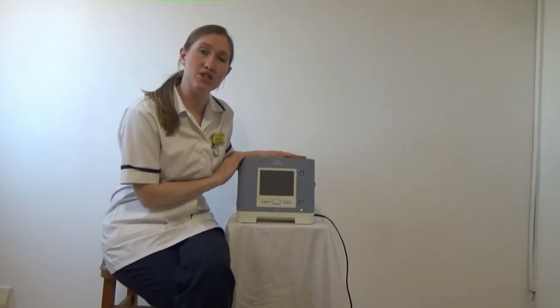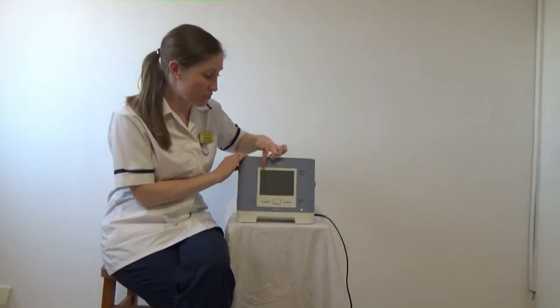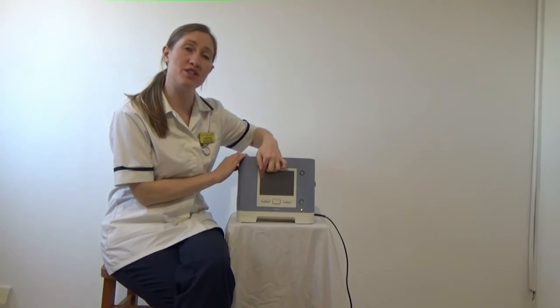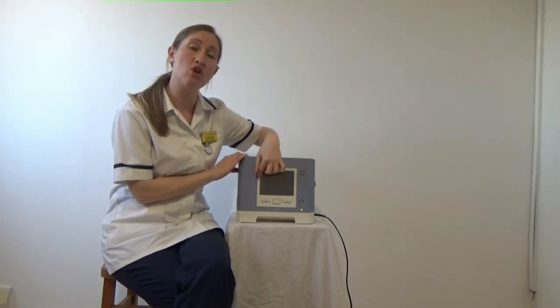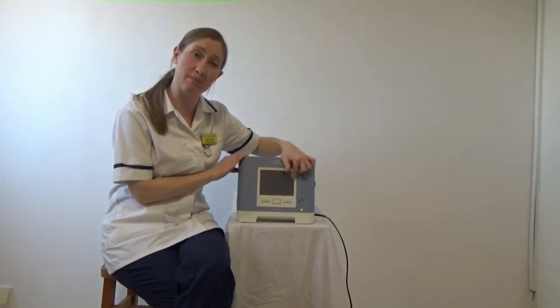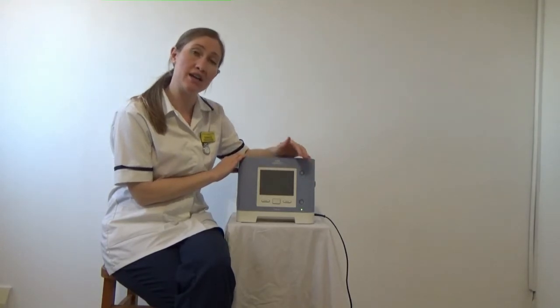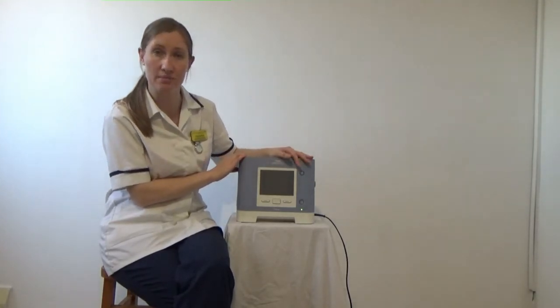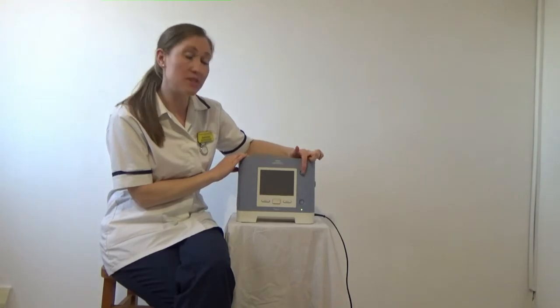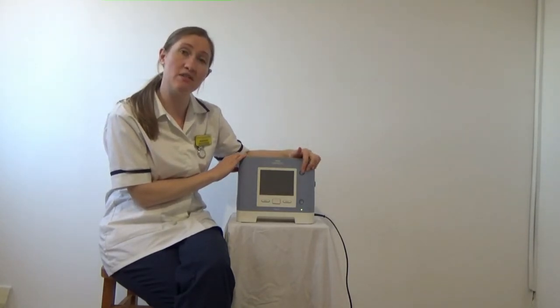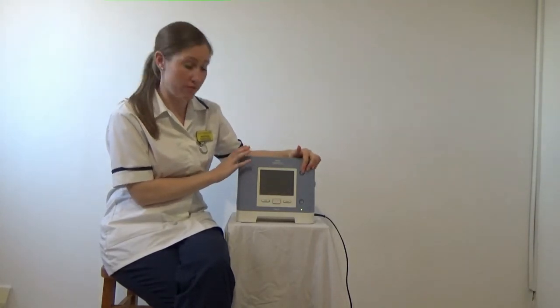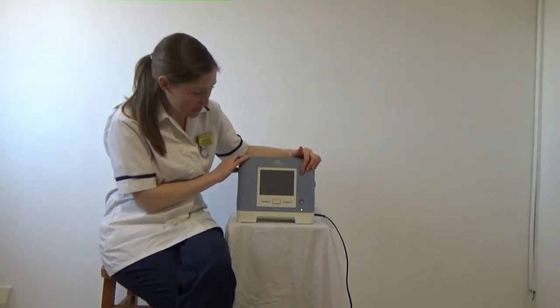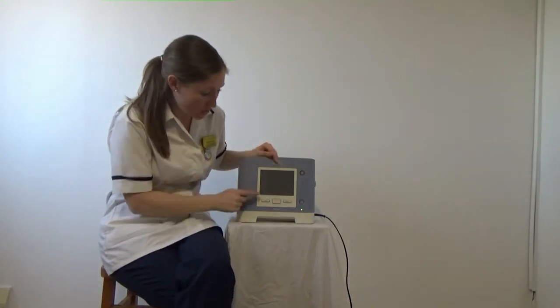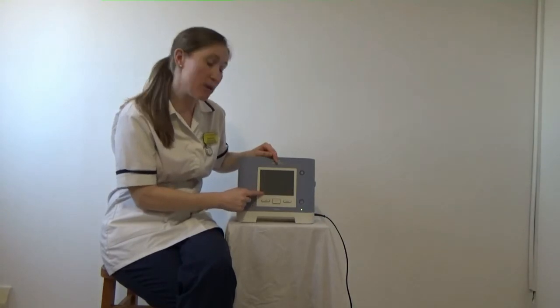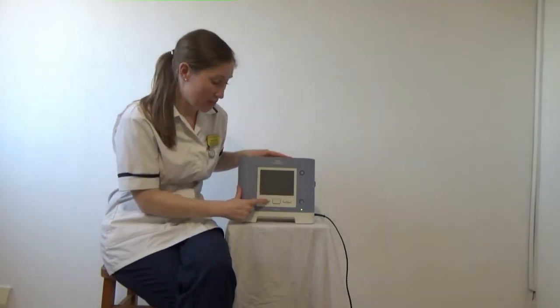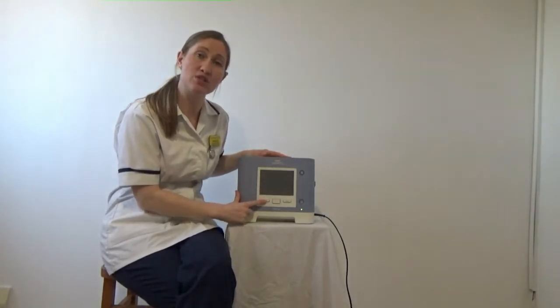If there are any issues with your ventilator, it will alarm. This will show up on the screen and will either show up as a red bar or a yellow flashing or yellow solid bar to represent high, medium and low priority alarms. This alarm silence button will silence the alarm for 2 minutes whilst you figure out the problem and resolve it. Once you have resolved the issue, this here will show up with a blue bar saying reset. Press the button just below it to reset the alarm.